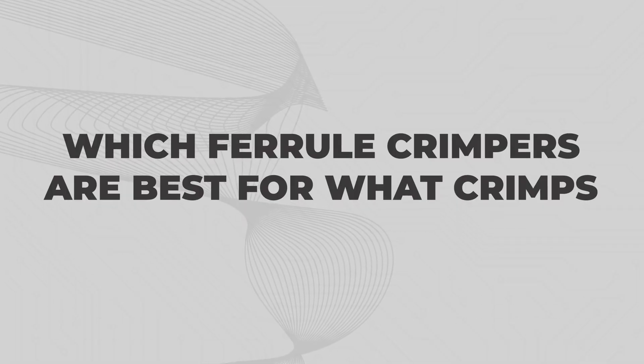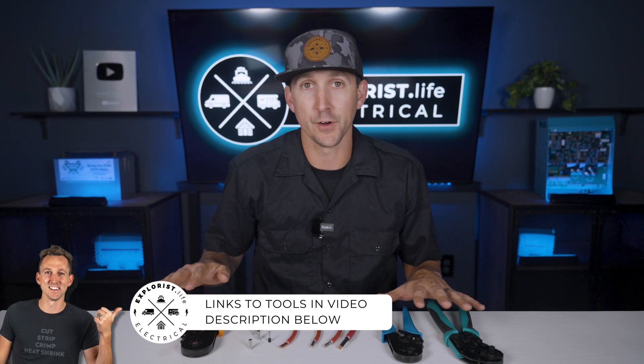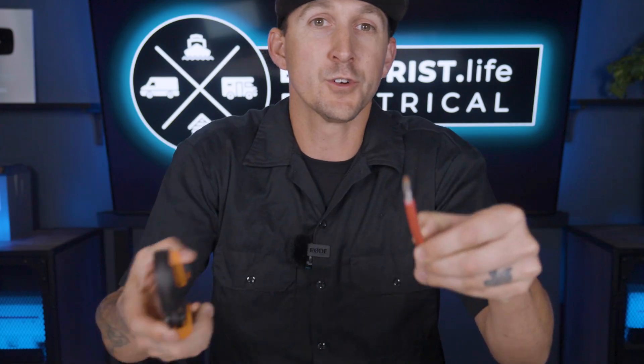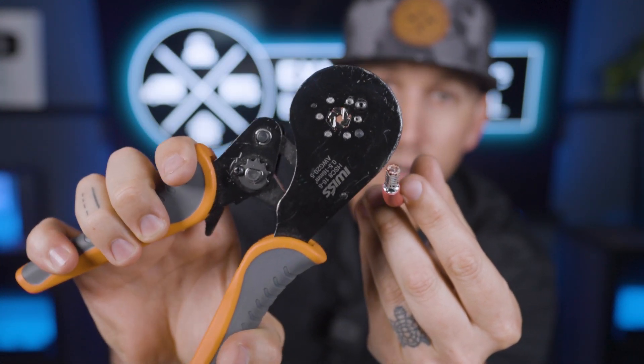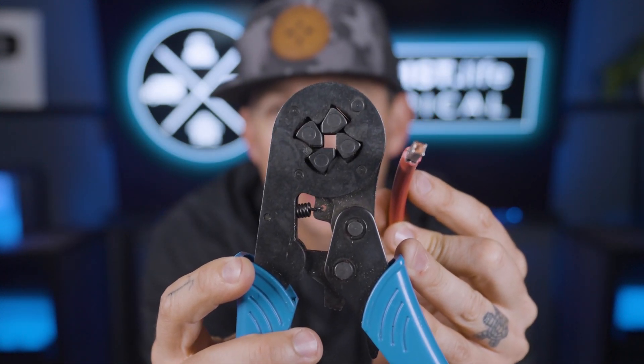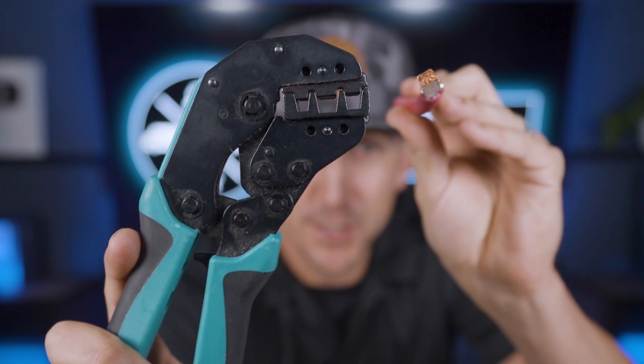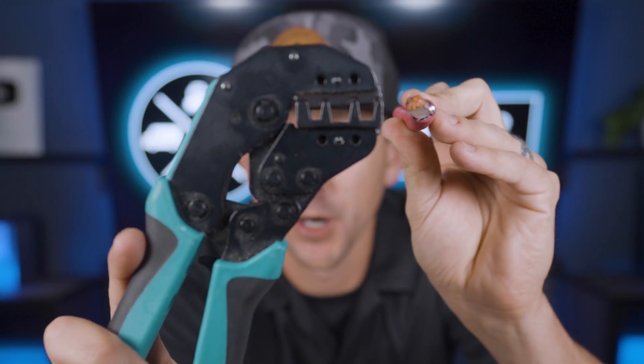Which ferrule crimpers are best for what crimps? I have three different types of ferrule crimpers here which covers all the different shapes and sizes of ferrules that I might need to crimp. These crimpers crimp a hexagon shape onto wires 6 gauge and smaller for round screw terminals. These crimpers crimp a square shape onto wires 6 gauge and smaller for square screw terminals. And these crimpers crimp a trapezoid shape onto 6, 4, and 2 gauge wires for square screw terminals.